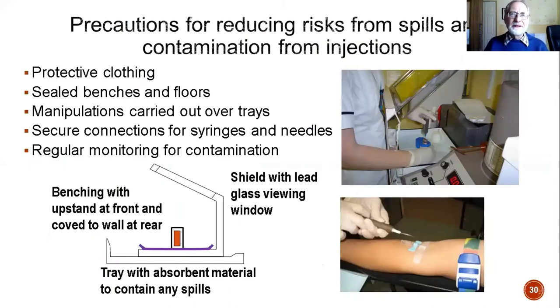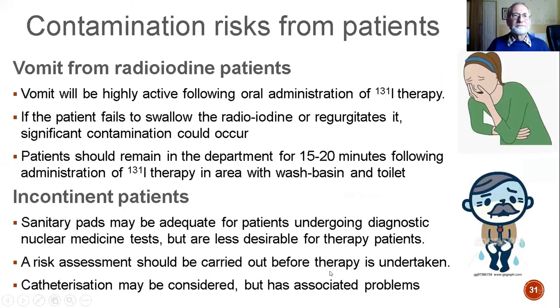Simple procedures should be in place in all radionuclide laboratories: protective clothing, sealed benches and floors, carrying out manipulations over trays with absorbent material to absorb any spill, secure connections for syringes and needles, and regular monitoring for contamination. All of these should help reduce the risk from any contamination event.